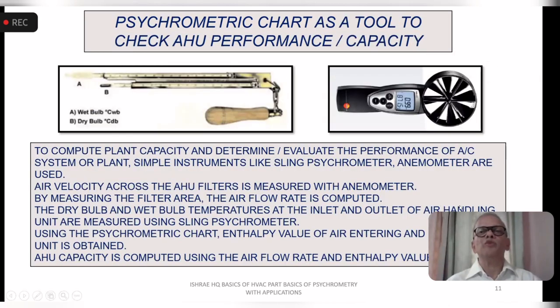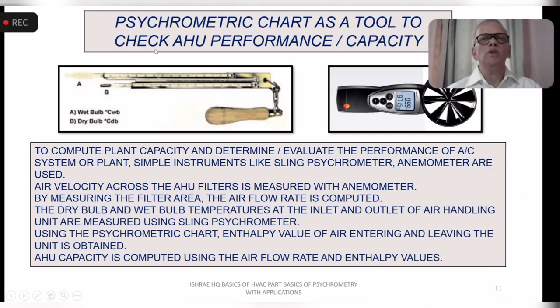Now, what we had seen before is measuring the air conditioning system performance. So the psychrometric chart is a tool to check the air handling unit performance and the capacity. These are the two tools which are very simple to use, and the skill level required to take these measurements is not very high. So we have AC mechanics who can check the dry bulb and wet bulb temperature using this sling psychrometer, and the anemometer, which will measure the air velocity. So to compute the plant capacity and evaluate the performance of the AC system or the plant, simple instruments like the sling psychrometer and the anemometer are used.